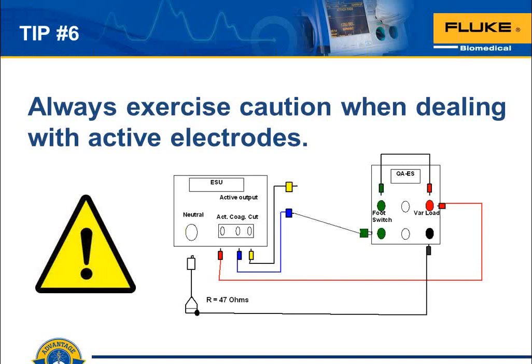Tip number 6. Always exercise caution when dealing with active electrodes. Now, I know how most of us are doing testing on electrosurgery units. We jury-rig or improvise connections all the time, and most of us are still using an alligator clip on the end of the single patient use disposable surgical pencil, with a little rocker switch that you can do cut or coag on. So we've got this blade there that's actually where the rubber meets the road during the actual surgery, using this generator to actually cut tissue or to coagulate bleeders. You don't want any possibility of anybody touching that blade.